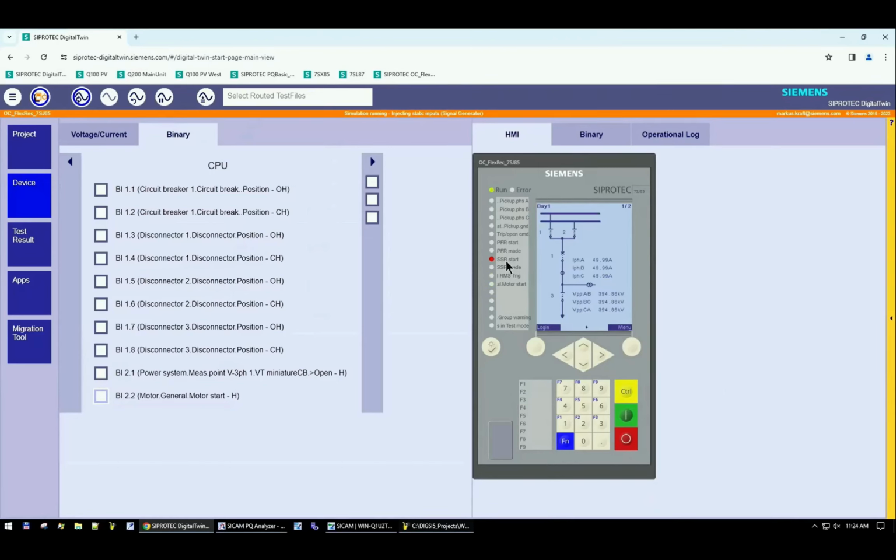I switch the signal off and now we have to wait these 6 seconds. This was the post-trigger time, and the green LED tells us, okay, the slow scan is made. Perfect. This SSR file or PFR file will now be communicated via IEC 61850 from the relay to the SICAM PQS substation automation system. And this PQS will now go down to the relay and upload this slow scan record via IEC 61850.